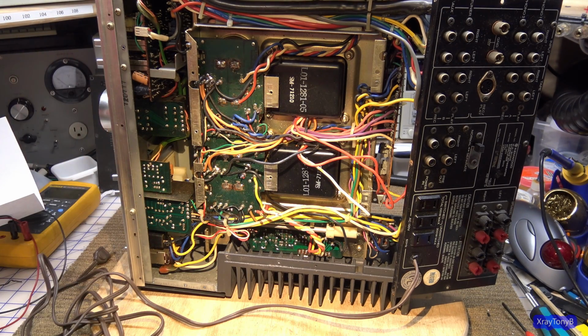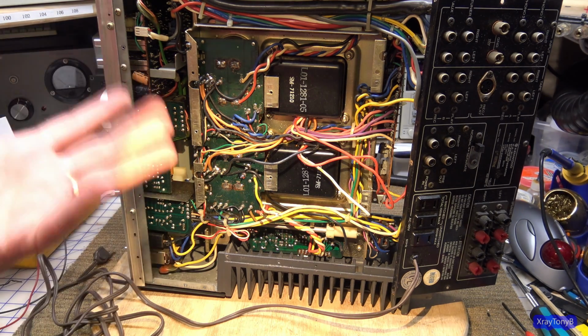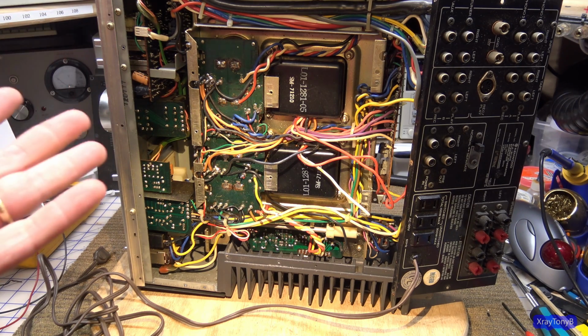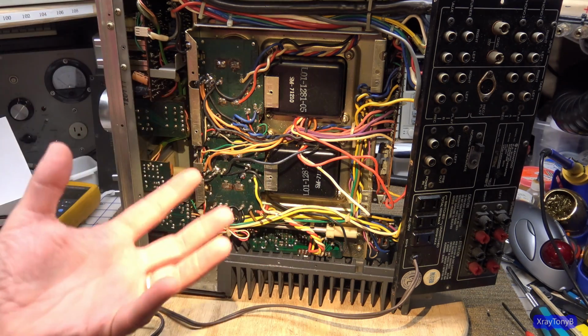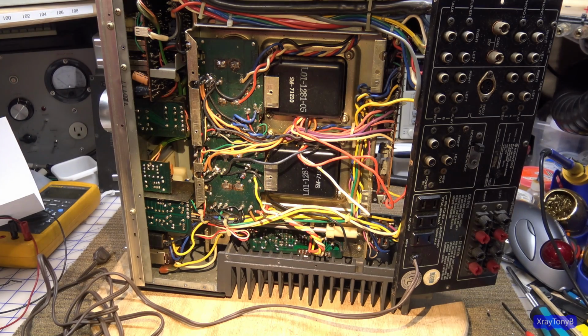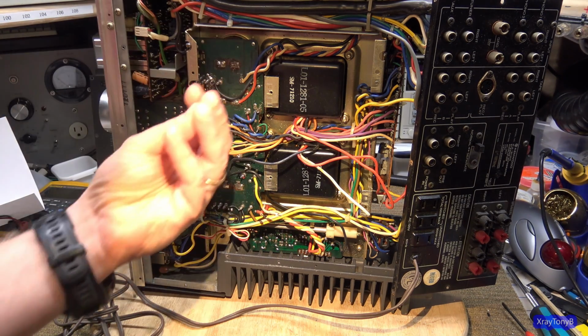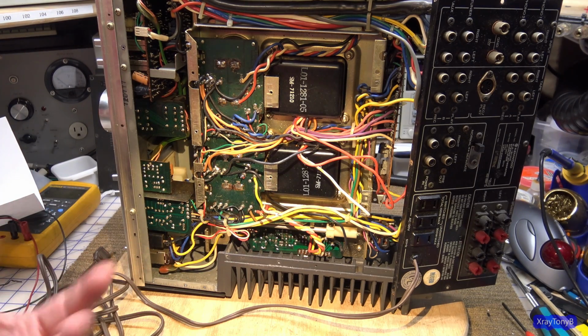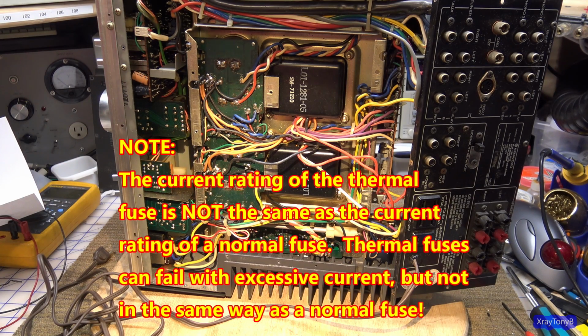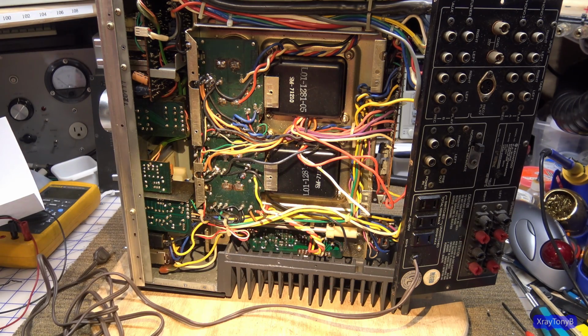Now, normally when that happens, there's a couple different failure modes of that fuse. They can fail, number one, just by age, just from thermal cycling, and then after a while they just open. They can fail from actually doing their job. If the transformer is overloaded for a long period of time and the coils get really hot, the fuse opens up. And the third thing is the actual current can be too high. So if you exceed the current rating of the thermal fuse, the fuse will open again, for instance, if you had a really hard short or something. Now, it's kind of weird that that opened up the way it did, being that you have a 2.5 amp fuse at the mains feeding it. But again, these can just fail from age and from thermal cycling.